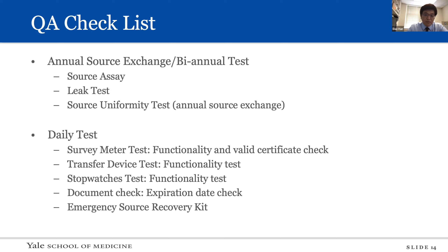Since the source half-life is around 30 years, the source activity does not change dramatically like other clinically used sources. However, the vendors want the device returned every year to maintain and adjust the mechanical and electrical parts. When we return the current device to the vendor, they send us another device. So we need to do the source check, the activity test, and the source uniformity test. Also, the NRC requires a source leakage test biannually. We collect the fluid from the device and give it to the radiation safety officer, and they do the leakage test survey. Before each treatment, we also need to perform the daily QA test.